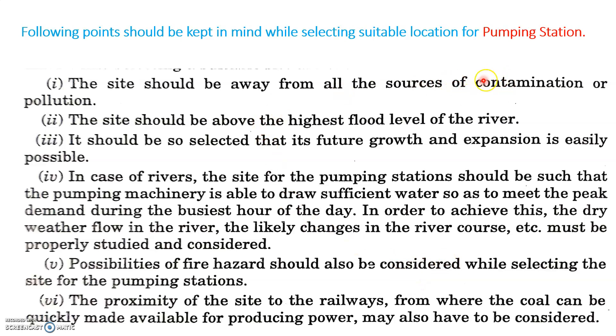There are certain points to keep in mind when selecting or locating a pumping station. First, it should be far away from any contamination or pollution zone. Second, it should be above the high flood level, because if placed at a lower level, the pump will be submerged during flooding and cause damage. Third, the location should allow provision for future growth and expansion. Fourth, if placing the pump near a river, it should allow withdrawal of sufficient water during peak demand and even in the dry season.